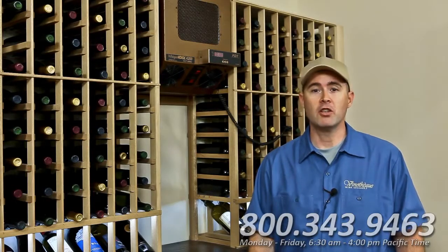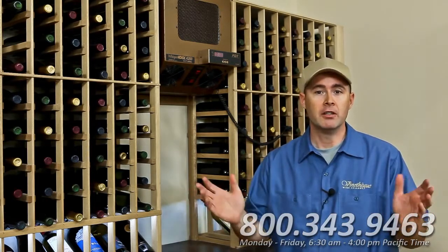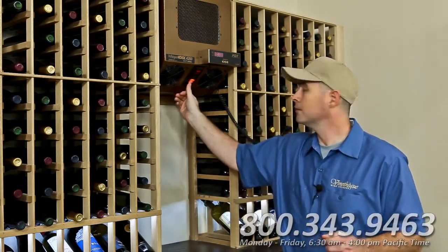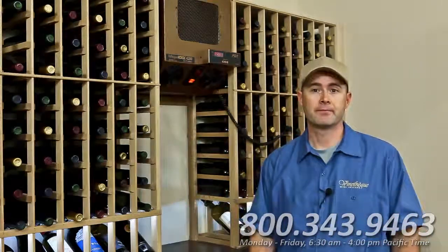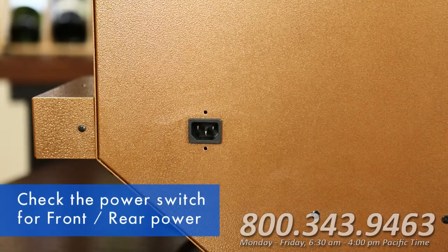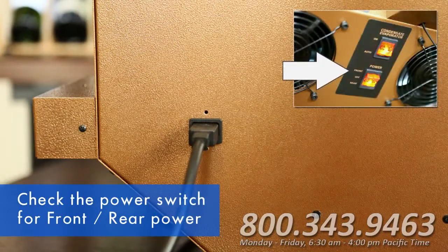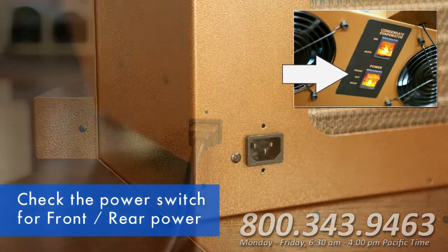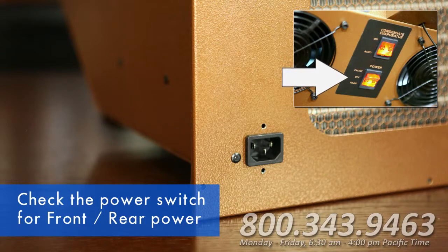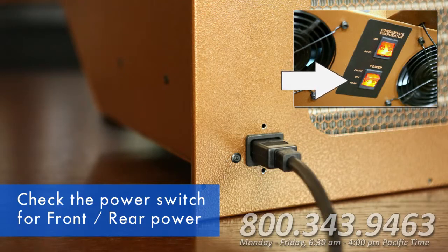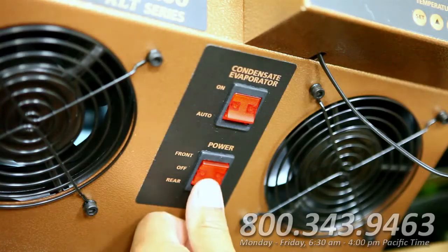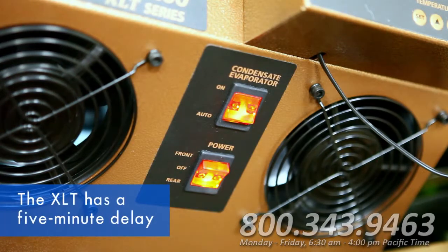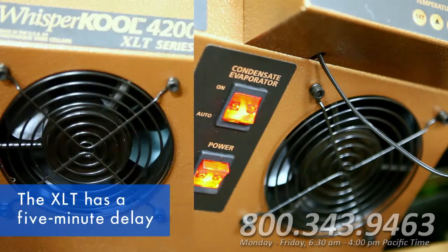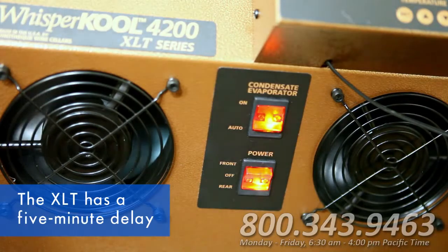Now, let's talk about what to do if your cooling unit is just not running. You flip the switch to on, but nothing happens. First, newer XLT units have two power inlets and a front-rear power switch, where front is the cellar side and rear is the exhaust side. Check the power switch and make sure that you have the correct inlet selected. Remember that there is a 5-minute delay from the time you turn on the unit until the fans begin to spin, so make sure you wait and see if your unit will function. If there is no activity after 5 minutes, run the bypass test.